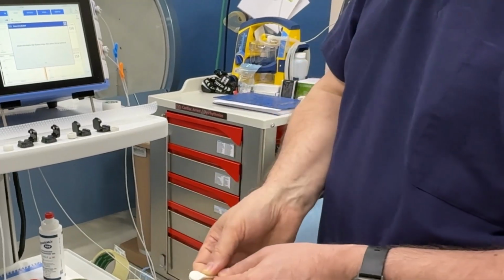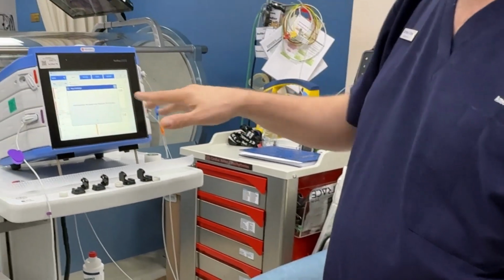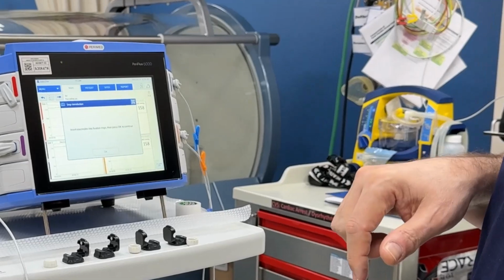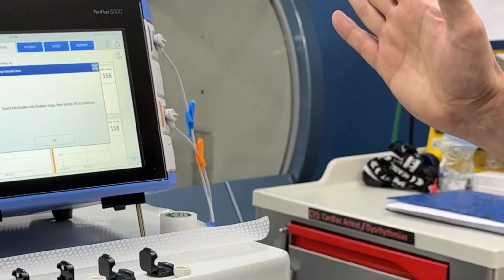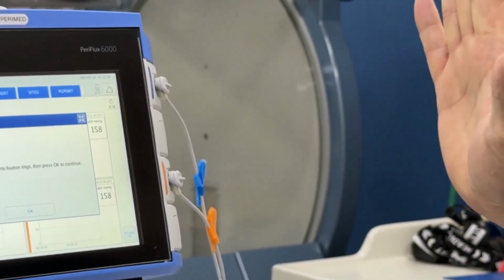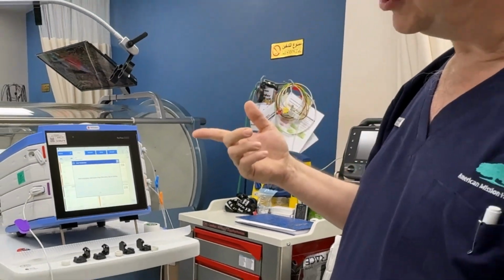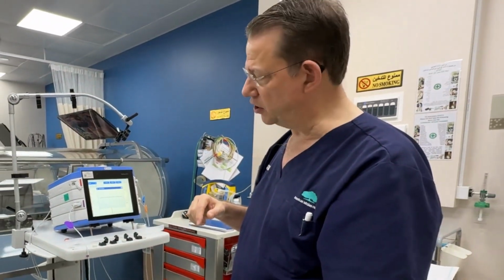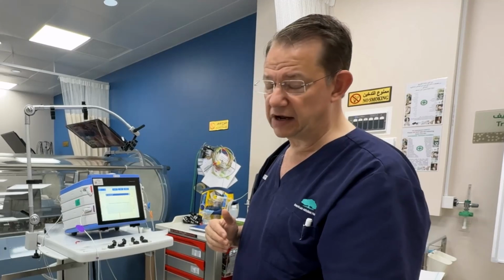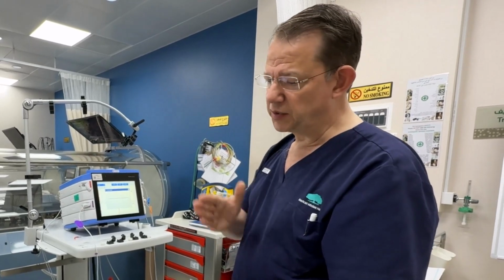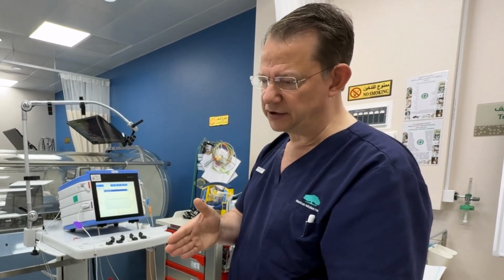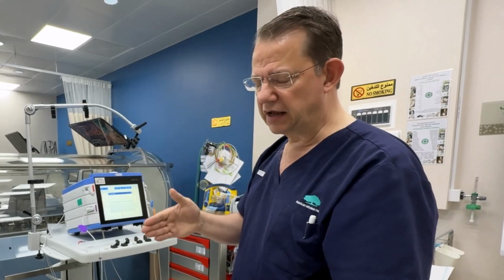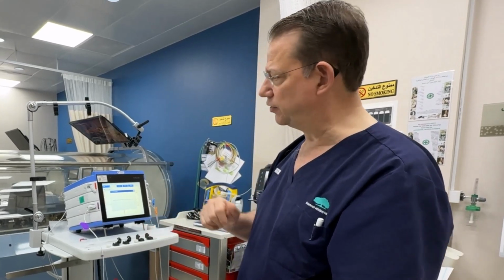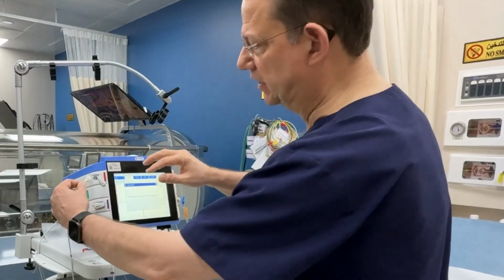The electrode is locked in, and once all the electrodes are in place, you hit the OK button and the process will continue. It will measure for 15 minutes on air, prompt you to then put the patient on 100% oxygen, and it will then count another 15 minutes. So we have a 15-minute air value and a 15-minute normobaric oxygen value that we can derive from this particular configuration.